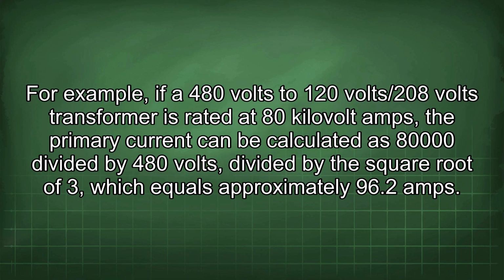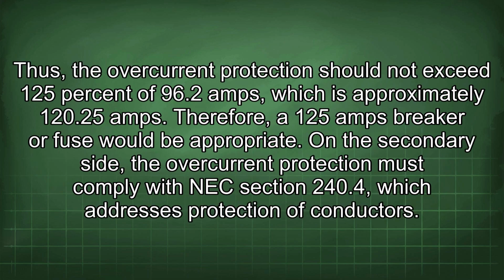For example, if a 480 volts to 120/208 volts transformer is rated at 80 kilovolt-amps, the primary current can be calculated as 80,000 divided by 480 volts, divided by the square root of 3, which equals approximately 96.2 amps. Thus, the overcurrent protection should not exceed 125% of 96.2 amps, which is approximately 120.25 amps. Therefore, a 125 amp breaker or fuse would be appropriate.